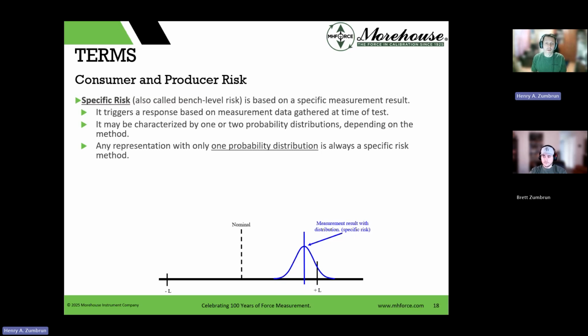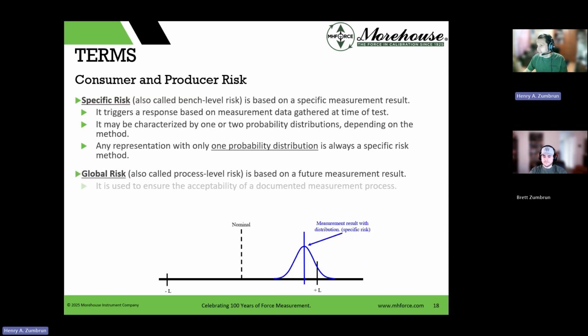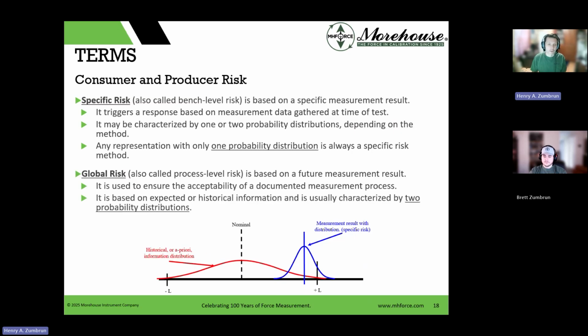Aaron throws the ball, it either goes in the target or it doesn't. It's gathered at the time of test. Characterized by 1 or 2 probability distributions depending on the method. Anything represented with 1 probability distribution is always specific risk. So Aaron throws the ball, it goes in or doesn't go in. So now we deal with global risk, also called process level risk. Based on future measurement results, it is used to ensure acceptability of a documented measurement process and based on expected historical information and usually characterized by 2 probability distributions.